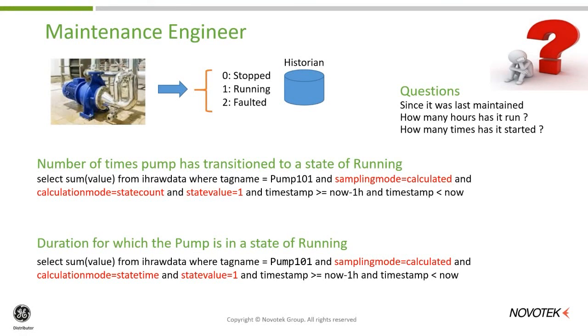There are OLEDB enhancements you wouldn't find in an ordinary SQL server. We have specialized terminology like state count and state value. In this case, I ask how many times pump 101 has transitioned to running state (state value = 1), using a sampling mode of 'calculated' with a state calculation mode of count. Similarly, using state time rather than state count, I can ask how long a pump or process has been in a particular state.